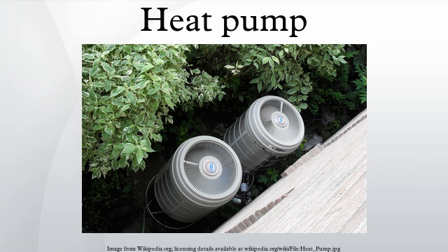Types: compression versus absorption. The two main types of heat pumps are compression and absorption. Compression heat pumps operate on mechanical energy, while absorption heat pumps may also run on heat as an energy source. An absorption heat pump may be fueled by natural gas or LP gas, for example. While the gas utilization efficiency in such a device, which is the ratio of the energy supplied to the energy consumed, may average only 1.5, that is better than a natural gas or LP gas furnace, which can only approach 1.